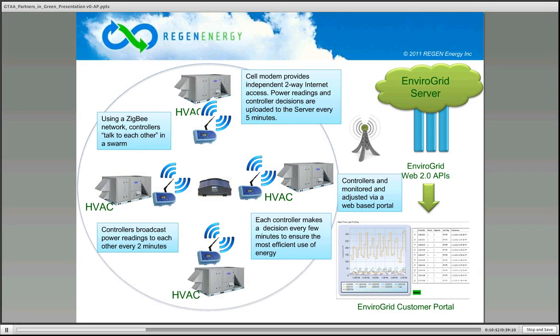We do this on a really warm day so that we know that on a really warm day, this unit needs to run 83% of the time to do its job. Then once we start the demand management profile, that unit will have 83% programmed in as its duty cycle, and it will run 2.5 hours out of 3.